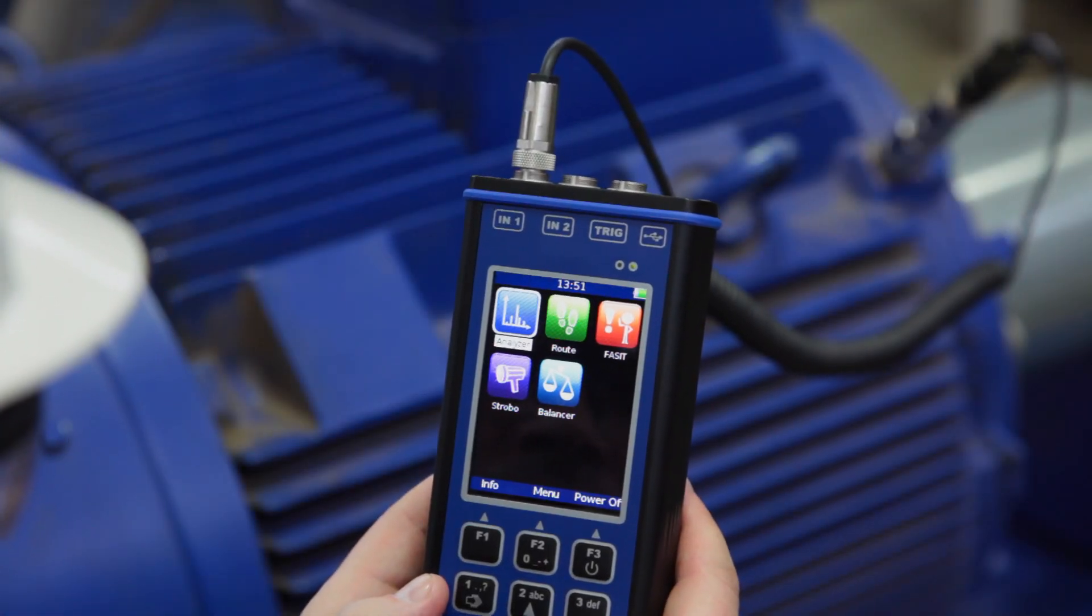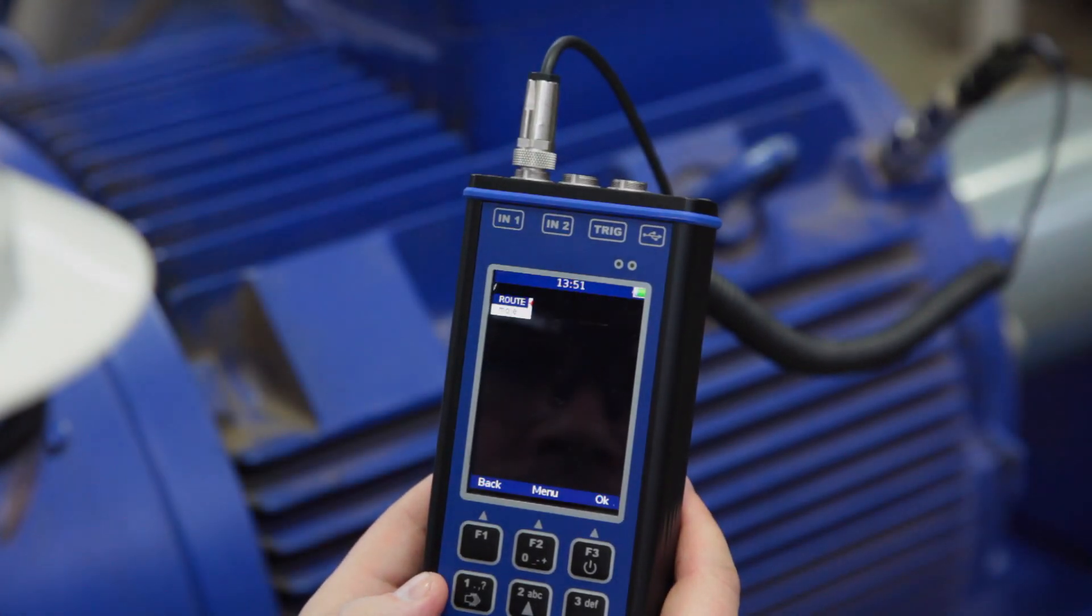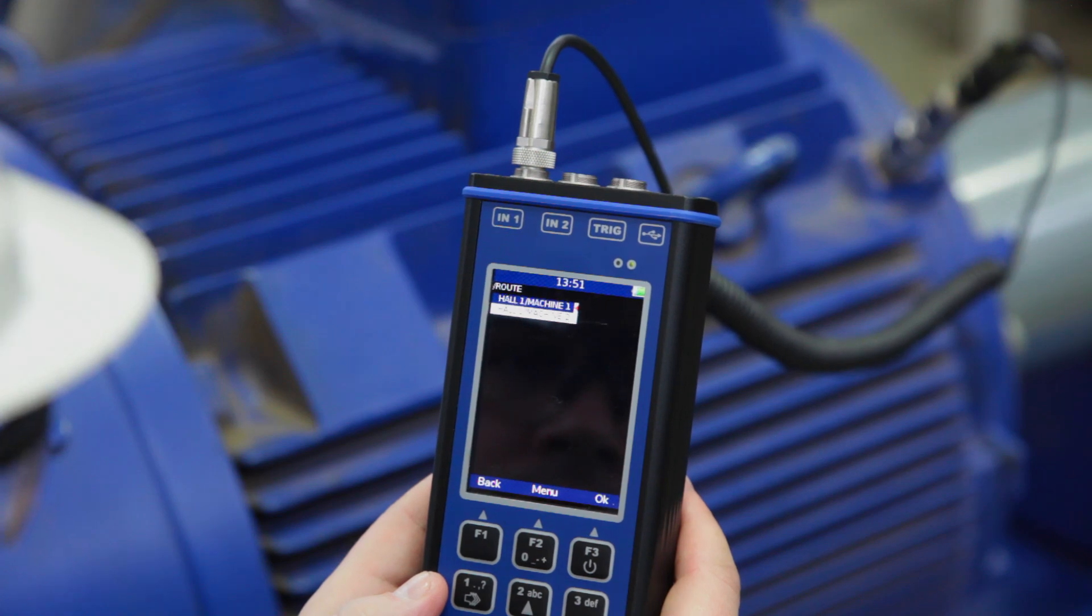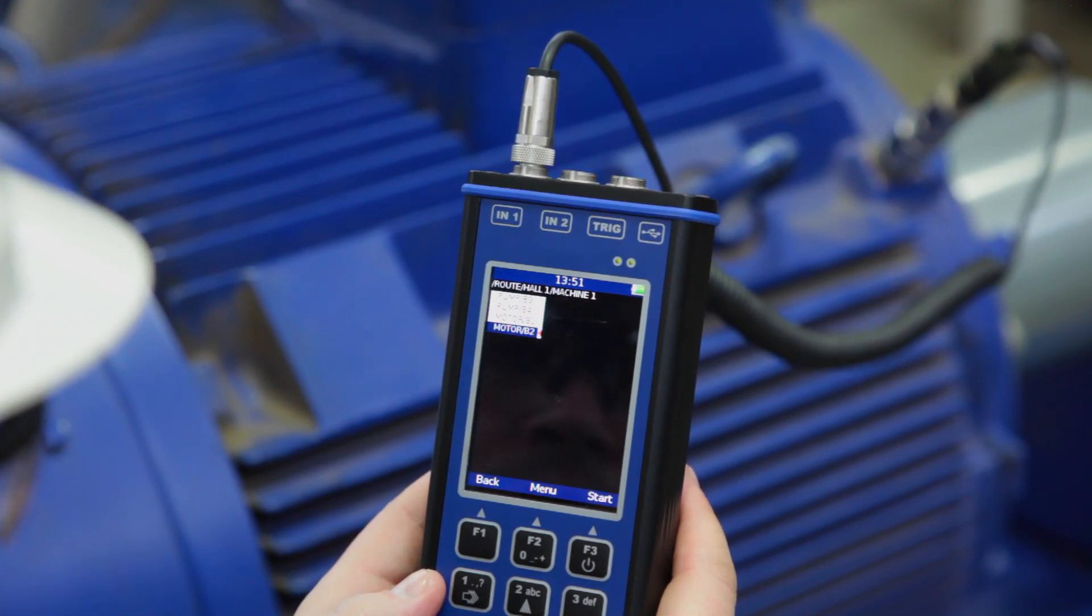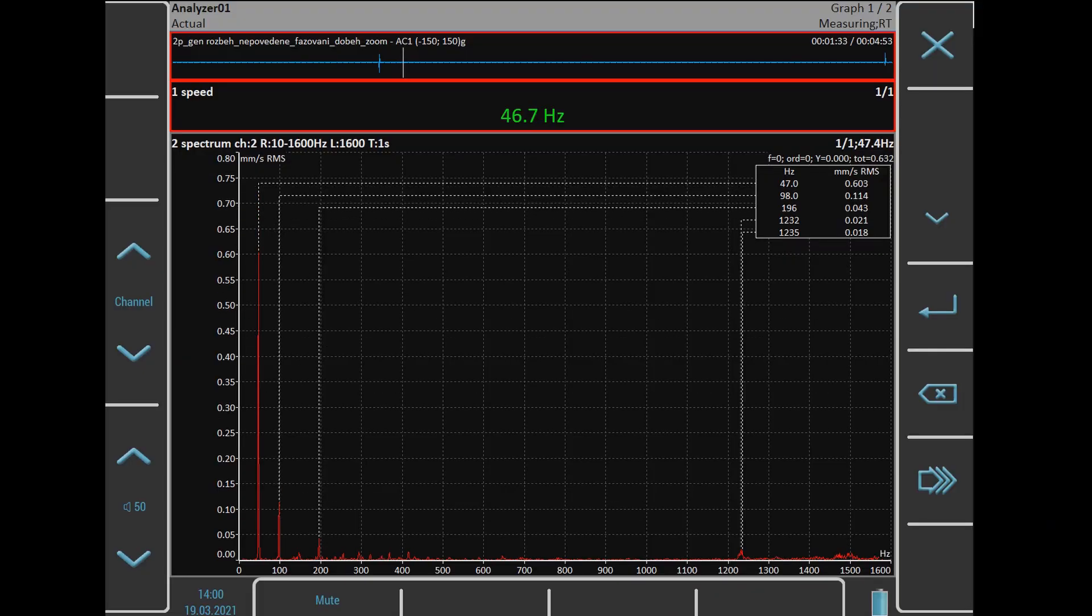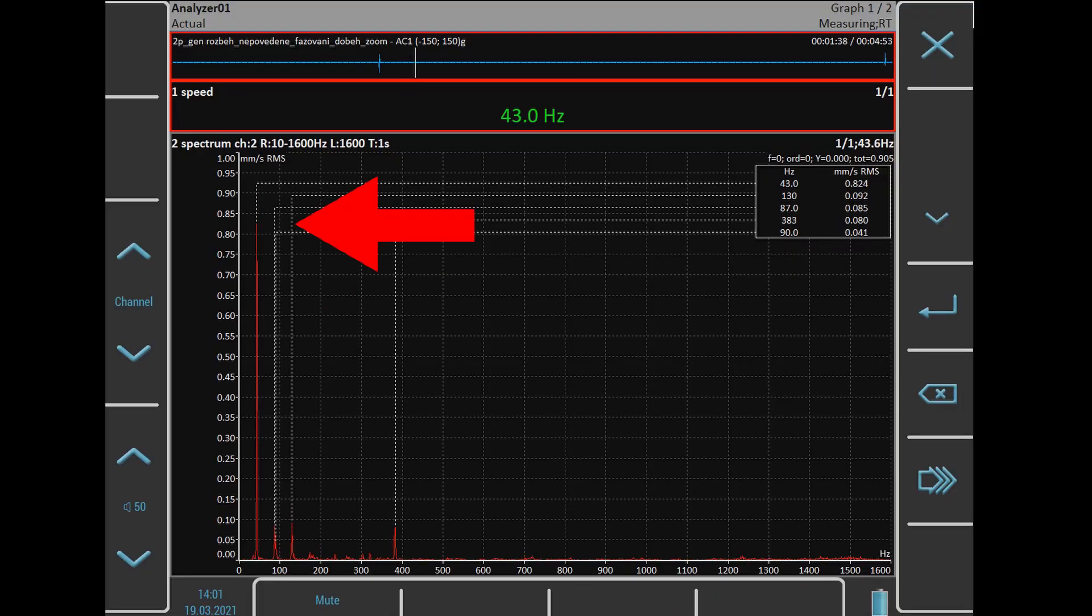Some electrical faults are recognizable in the vibration spectrum too. You should measure the motor with and without a power supply in order to find them. Some vibration signatures could disappear after power off, those with an electrical origin.